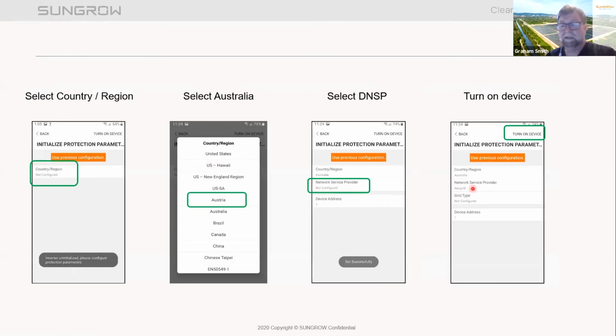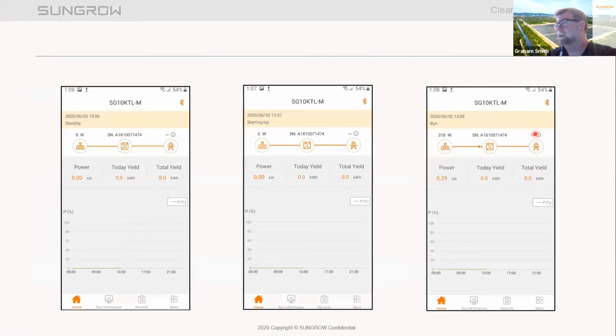You will get a list of the DNSPs, and all the settings are preloaded into that, so you don't have to actually change any of the settings unless your DNSP actually requests a different setting. So we've got all these settings here, and in this case, I selected the Ausgrid network. And then up in the top right hand side, it says turn on device, and you tap that, and you will get this screen here first of all. It will go into standby, then it will go starting up, the usual startup phase, then it will be on run. And once you've done that, the inverter is set for the grid connection.